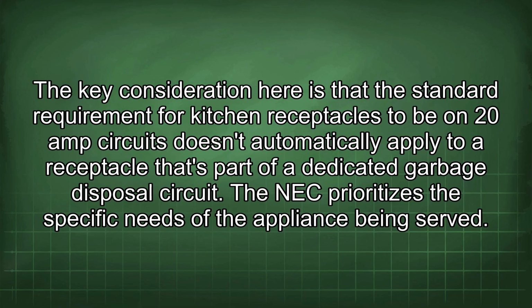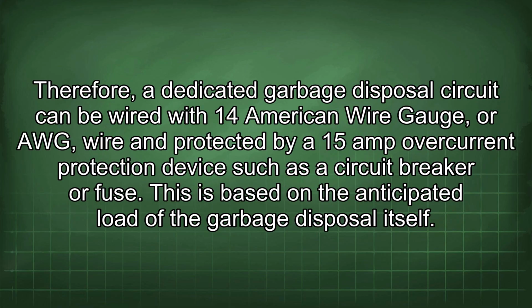The key consideration here is that the standard requirement for kitchen receptacles to be on 20-amp circuits doesn't automatically apply to a receptacle that's part of a dedicated garbage disposal circuit. The NEC prioritizes the specific needs of the appliance being served. Therefore, a dedicated garbage disposal circuit can be wired with 14 American wire gauge, or AWG, wire and protected by a 15-amp overcurrent protection device such as a circuit breaker or fuse.